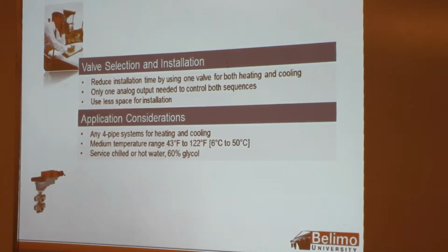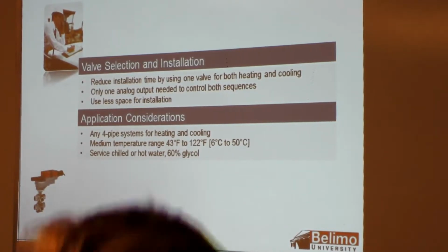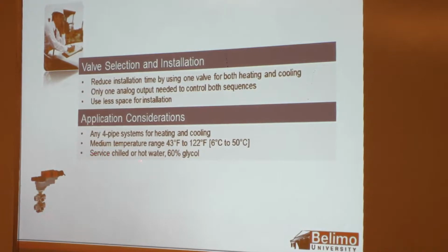Why did we develop this? Well, you can reduce your installation time by using the one valve for both heating and cooling. You only need one analog out rather than 2, and you're controlling both sequences that way. And it uses less space for your installation. So your application considerations: any 4-pipe systems for heating and cooling. Your medium temperature range is 43 to 122 degrees. And it has chilled water, hot water, and 60% glycol solution capability.